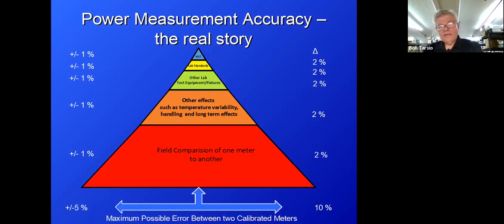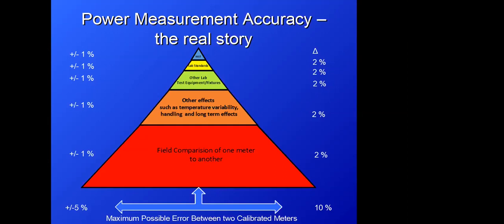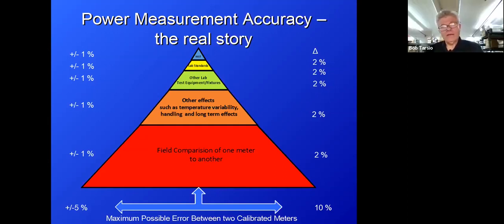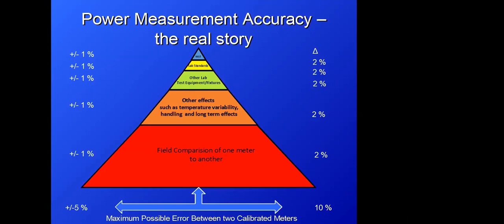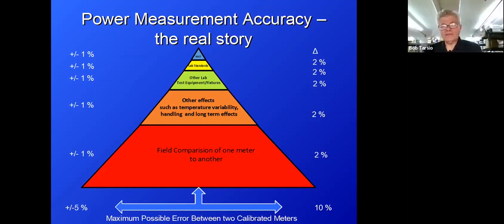So what this really means is once we've calibrated an RF sensor and we measure back, we can measure the actual absolute, let's say, simulate, because what we're really doing is we're simulating the output of the directional coupler at the precise level that we expect from the directional coupler for a given power level. And then we're looking at the actual indicated power based on that. And when we do that, so for example, we use a 60 dB standard, for example. So 0 dBm is 1 milliwatt.